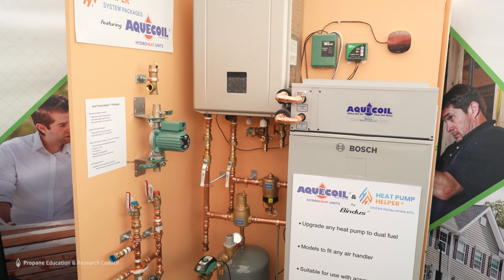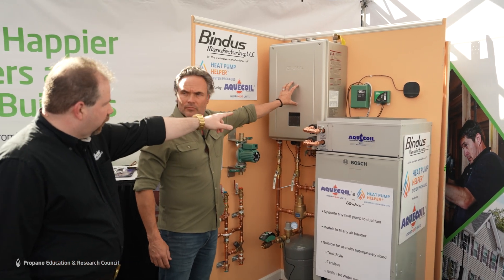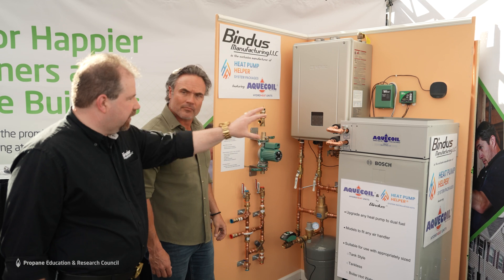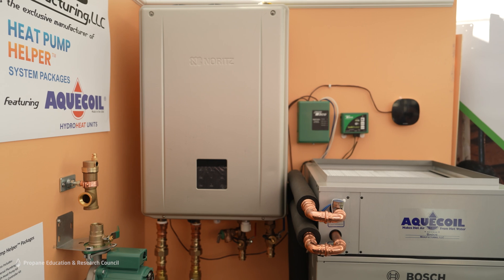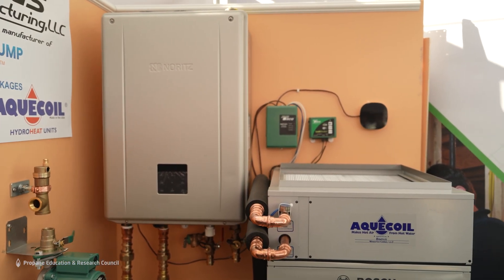When there's a call for heat from the wall thermostat, it sends a signal to the controller. The controller then activates the water system to start circulating water into the heat exchanger built inside the Aquecoil. Air is blowing from the air handler through that, and now you have radiator quality heat through your central air duct — capturing energy already being made by your boiler or your hot water heater and using it to heat the home.